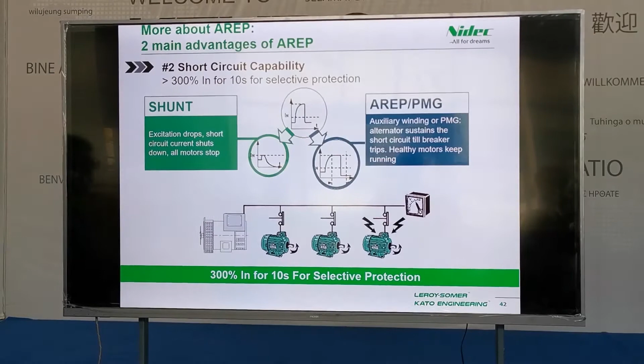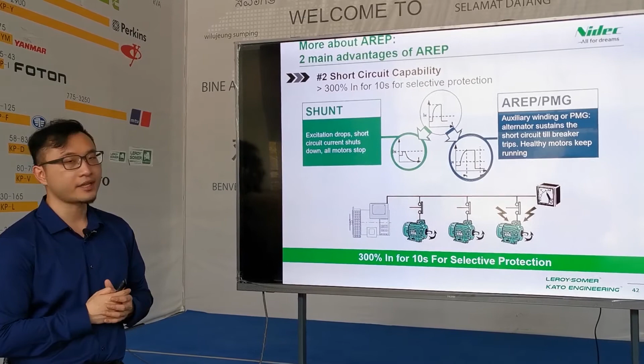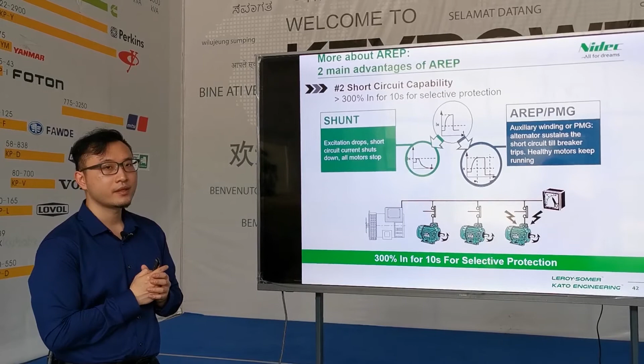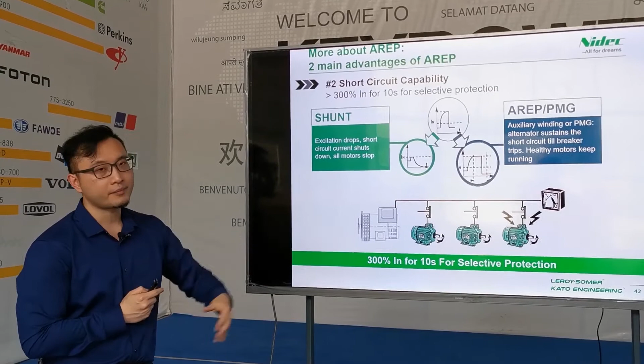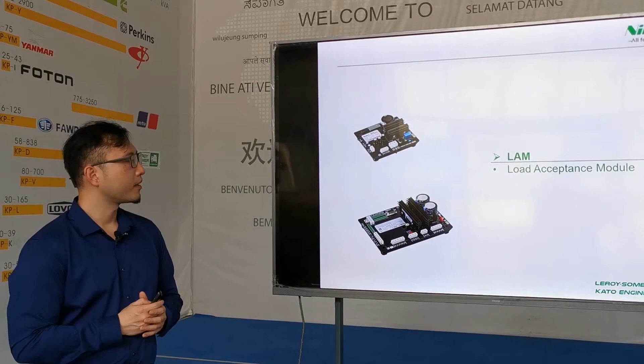And for short circuit capability, with the AREP/PMG excitation system, the alternator can have, for example, LSA has 300% of the rated current for 10 seconds for selective protection, which is a feature necessary for some applications like marine and also for parallel applications. And the second advantage is LAM, which is short for the load acceptance module.